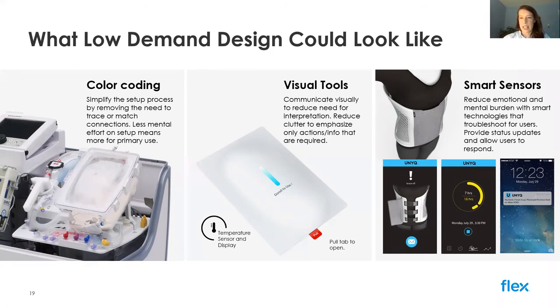For instance, in this case, this is a scoliosis brace intended to be used predominantly with young adults with scoliosis. So the first screen you see at the bottom here, it says, oh, brace is off. And so it's letting either the parent or the child know either your brace is too loose and I think it's off, or it's telling the parent, hey, your child isn't being compliant, even though they're supposed to be. Maybe they took it off at school to have fun, so if you check and you think that it's not a time they should be having it off, then that's a good way of just reminding them why they're doing it. It allows you to not worry about, I wonder if they're keeping the brace on.